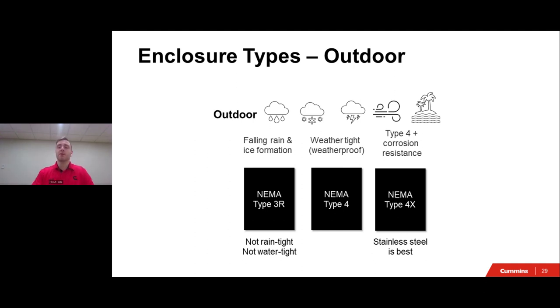And then lastly, we have our Type 4X enclosure. The Type 4X enclosures are the same as the Type 4. However, the only difference being the 4X is constructed with corrosion-resistant material. NEMA and the industry defines corrosion resistance as constructed to provide a degree of protection against exposure to corrosive agents such as salt spray.